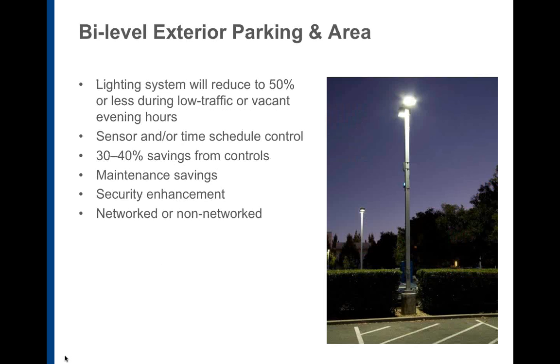So those lighting systems reduce to 50% or less during low traffic or vacant evening hours, and should be equipped with sensors and possibly time scheduling controls. And you get that 30 to 40% savings from those controls. And of course, we saw those estimates for relamping both inside and out, so the maintenance savings are evident.